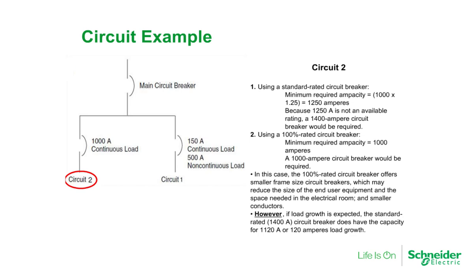However, if load growth is expected in the circuit, the standard rated 1400A circuit breaker does have the capacity for 1120A, or in other words, 120A of load growth.